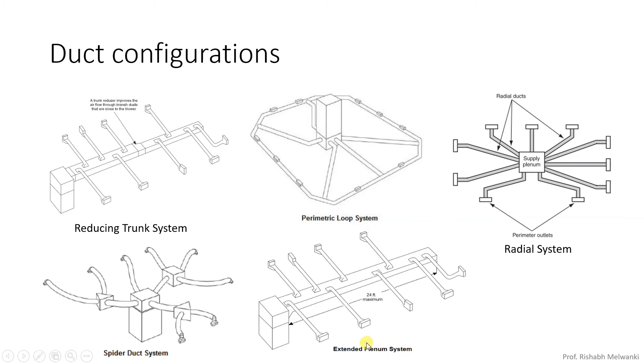In the extended plenum system, here you can see this is the plenum and this is a trunk. We have branches, and here you can see the dimension is the same in the extended plenum system. Next if you consider the spider duct system: this is the supply plenum and from here we have these branches, also called runouts, which are connected to air terminal units. So this is called spider duct system.